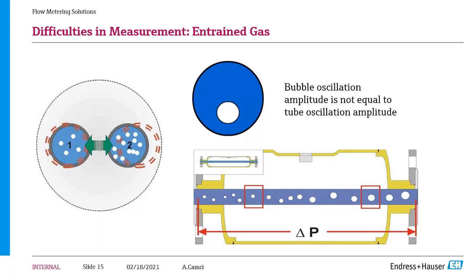Second, the air bubbles will not equally distribute between the two tubes available in the Coriolis meter. This will create an additional measurement error. And due to the pressure change inside the meter, the bubbles will get bigger in size. The size of the bubbles will change, and it will also create a measurement error.